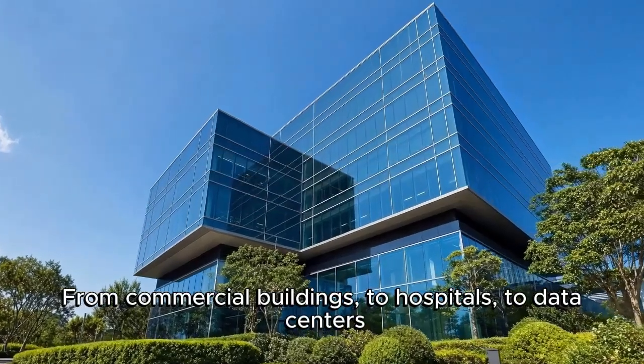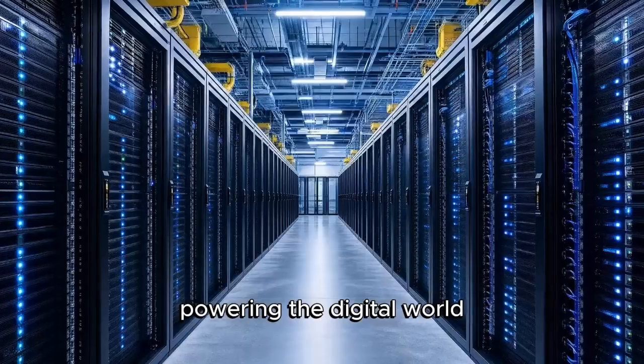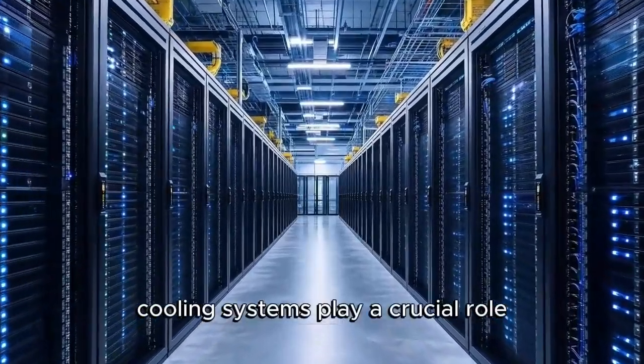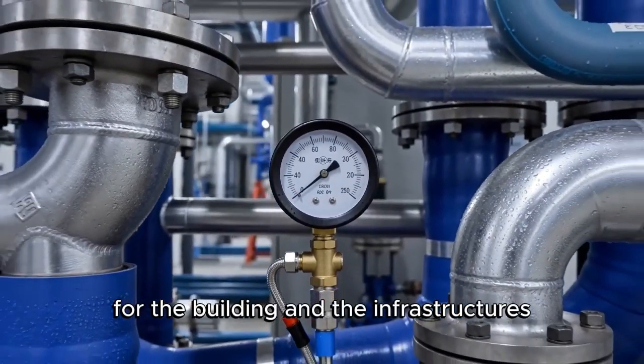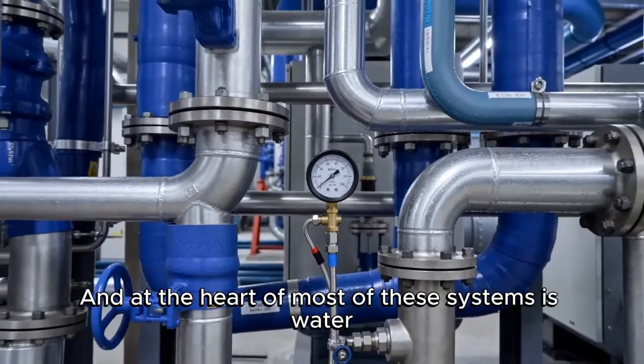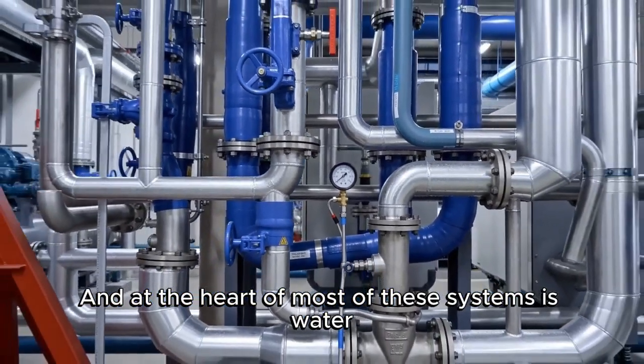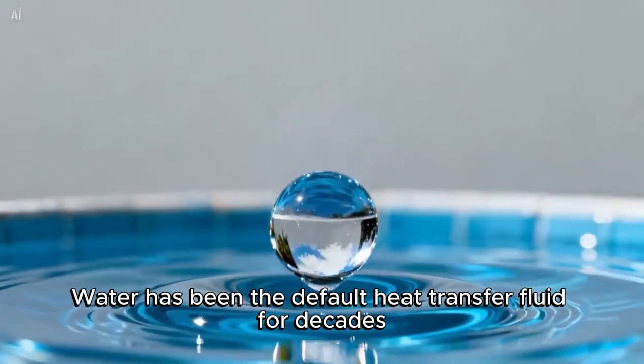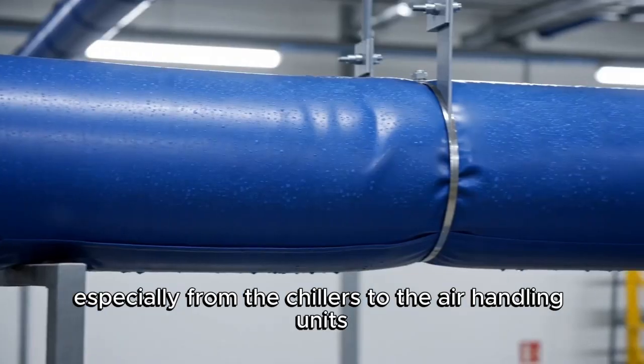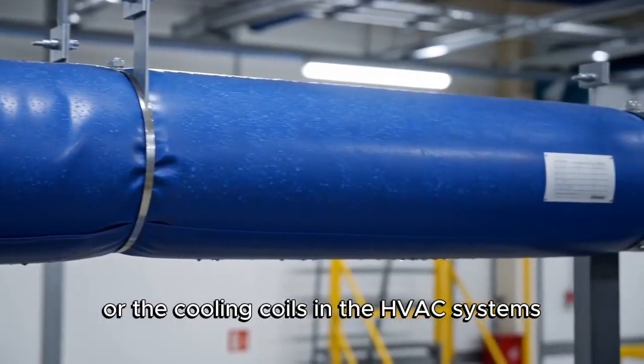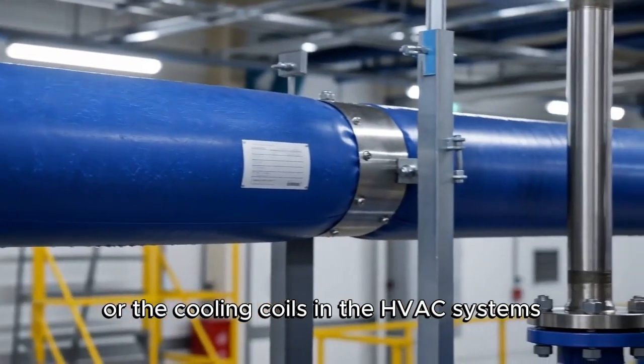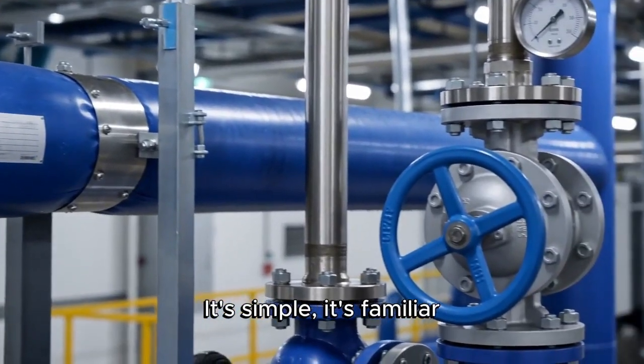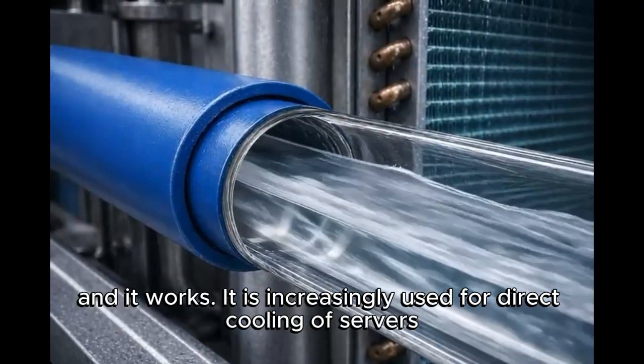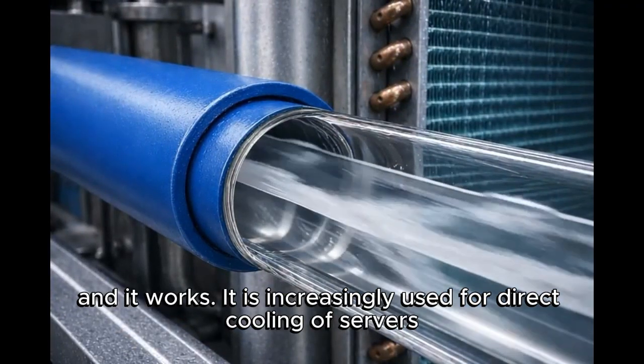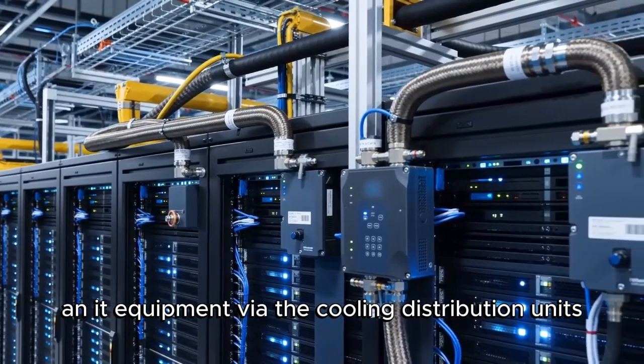From commercial buildings, to hospitals, to data centers powering the digital world, cooling systems play a crucial role for the building and the infrastructures. And at the heart of most of these systems is water. Water has been the default heat transfer fluid for decades, especially from the chillers to the air handling units or the cooling coils in the HVAC systems. It's simple, it's familiar, and it works. It is increasingly used for direct cooling of servers and IT equipment via the cooling distribution units.